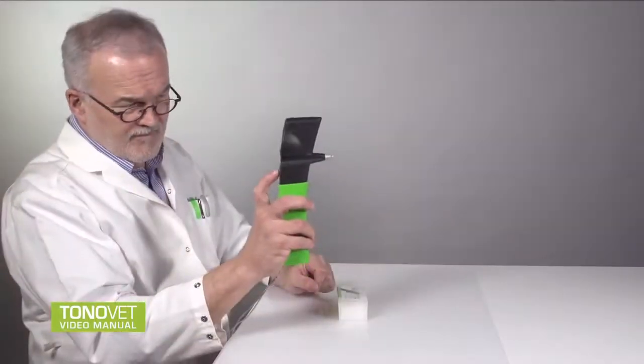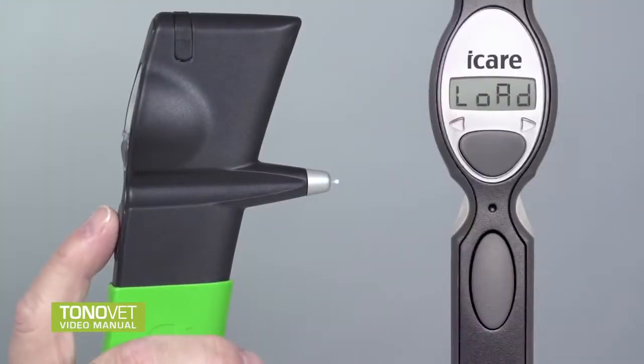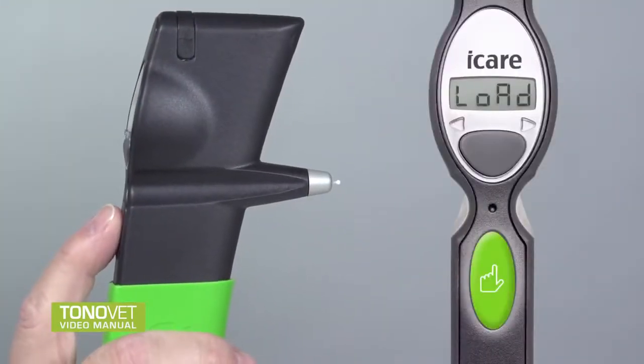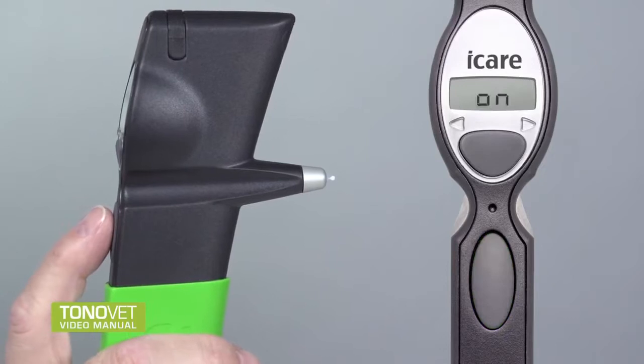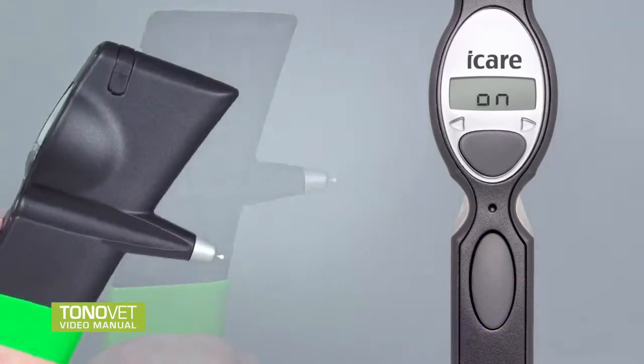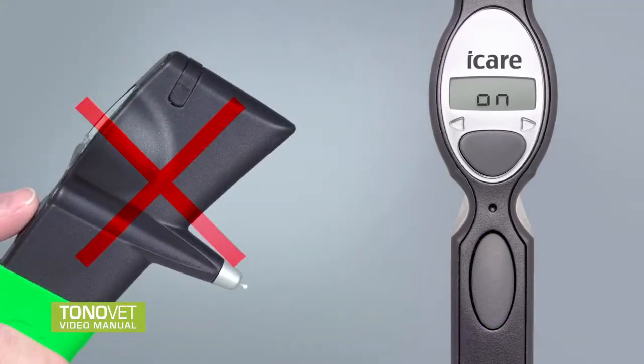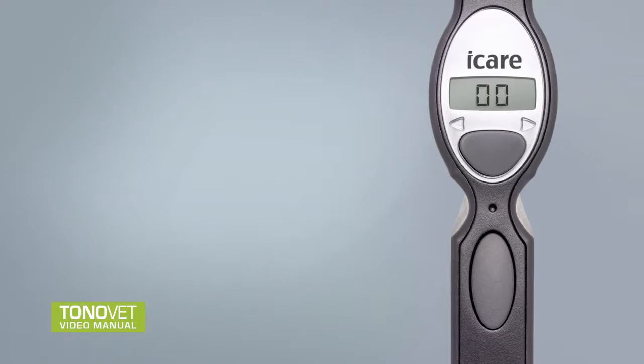Activate the magnetic field which holds the probe in the probe base by pressing the measurement button once. Be careful not to point the tonometer down before the magnetic field is activated, as there is nothing holding the probe. The tonometer is ready for the measurement when the display shows 0, 0.